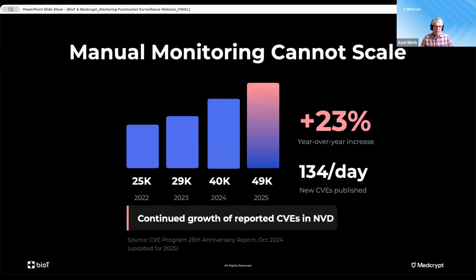Vulnerability monitoring and supply chain management, obviously one requirement that is very consistent across the globe and is getting more challenging over time, right? Here is a view of the last couple of years, the number of vulnerabilities published in the US National Vulnerability Database, short NVD. Right, we have seen a 20-30% range increase year over year over the last couple of years. Right now, we are running around 130 new vulnerabilities per day. And you, as a device manufacturer, are expected to stay on top of that, to filter the information that is relevant to you and to your customers from the noise, right? Because of those 49,000 vulnerabilities that came out in 2025, only a small portion affects you, and only a smaller portion of that is actually security relevant and safety relevant to your devices. So again, efficiency here is key.